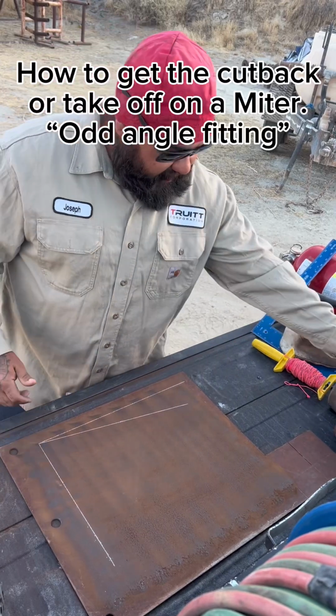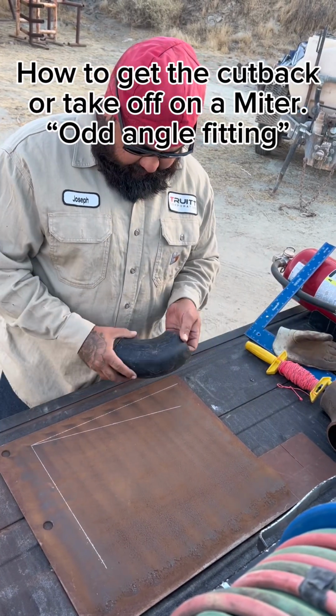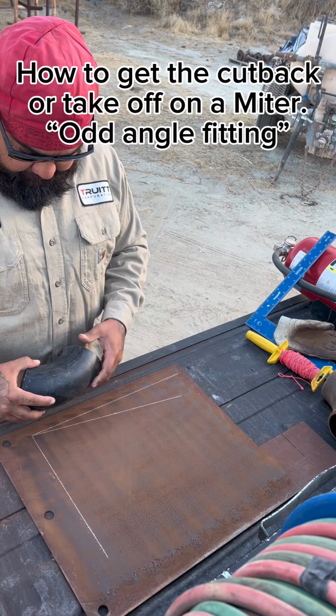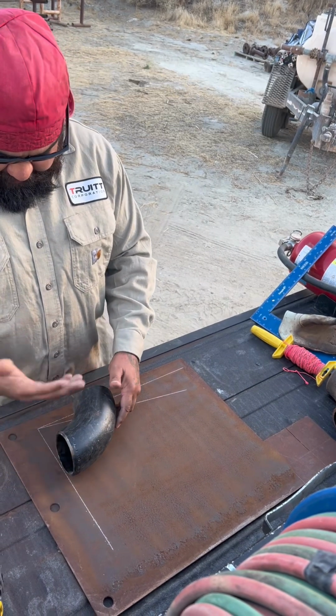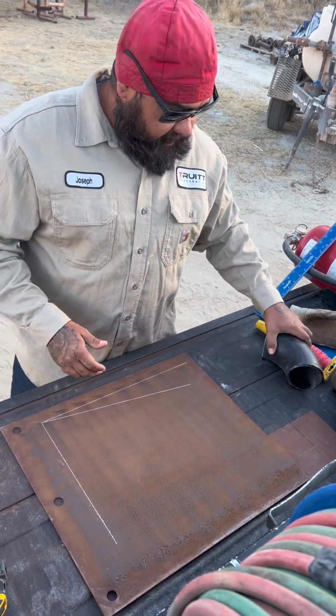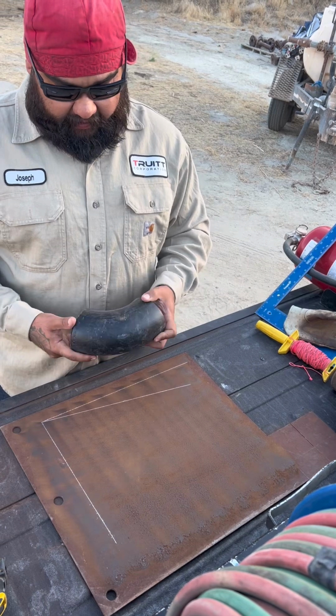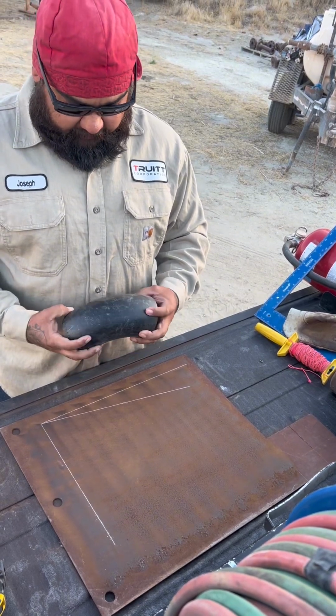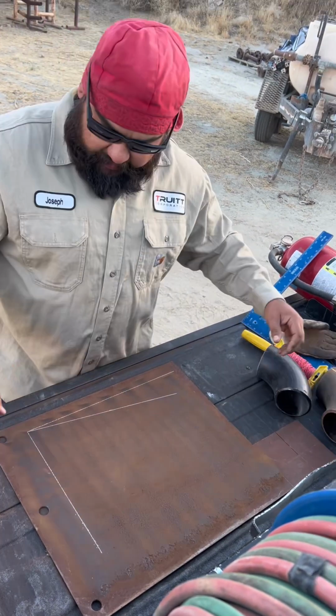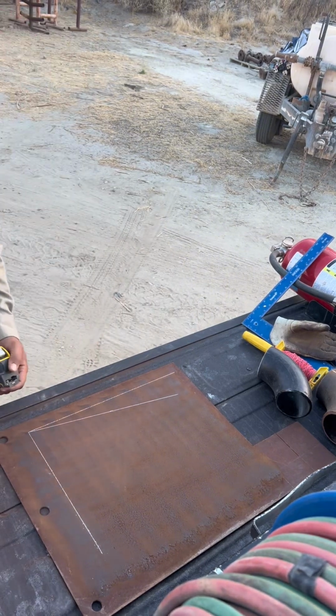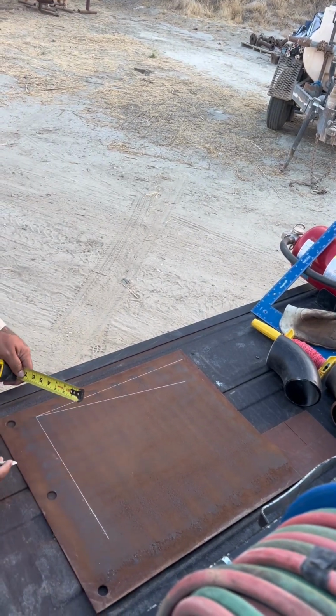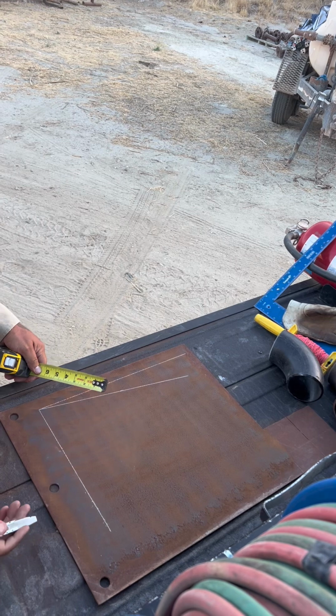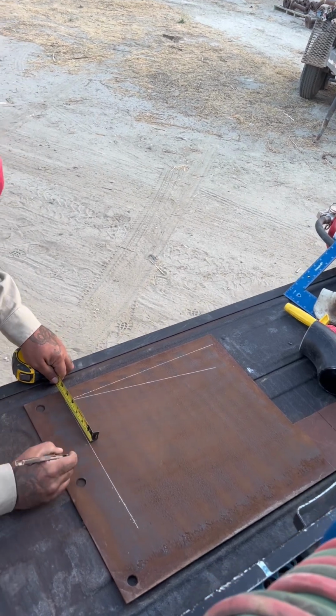Once you've already found your miter, you drew it out, you got your cut, right? You cut everything, it looks good. Well, now you got to figure out the cutback on this odd angle miter, right? So what you can do is you're gonna get your tape measure. You measure up from this corner right here to get center of the fitting. This is a 3-inch pipe, so we're gonna go 4.5 up.